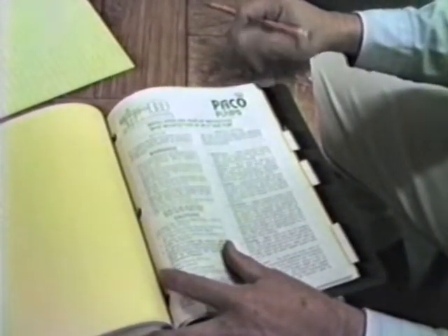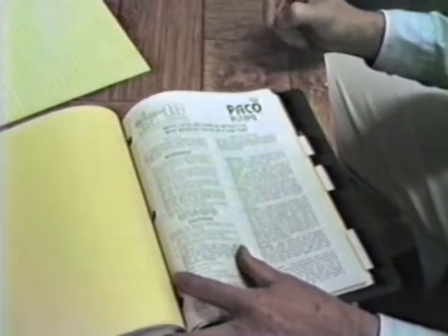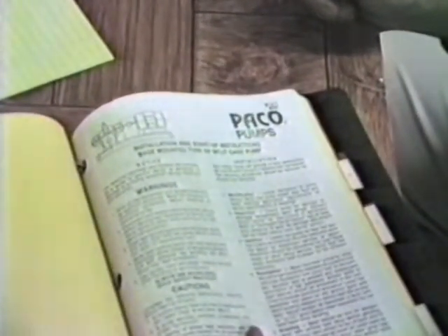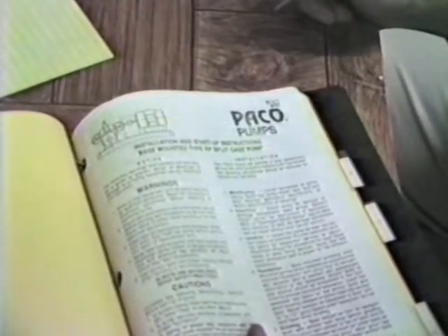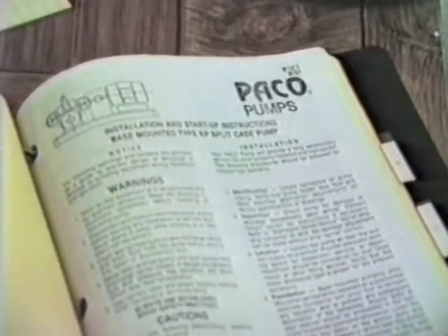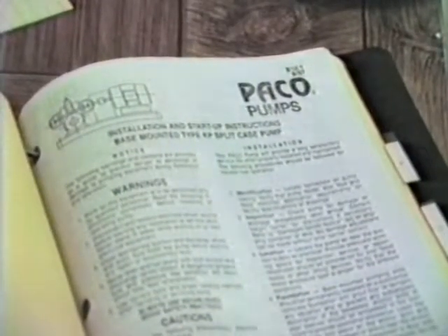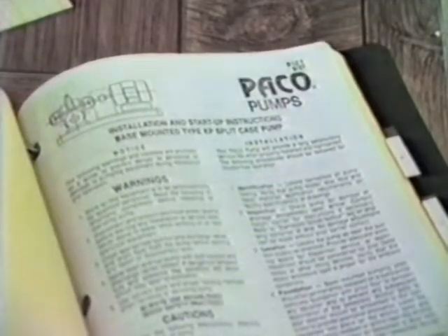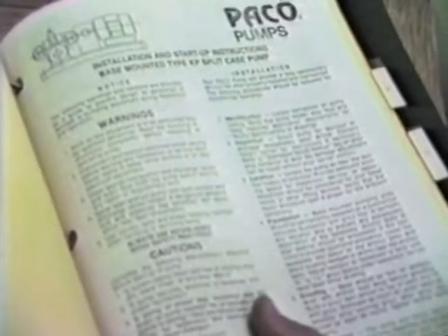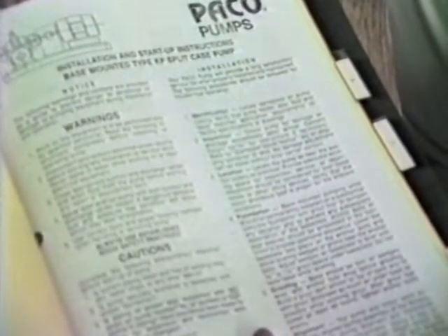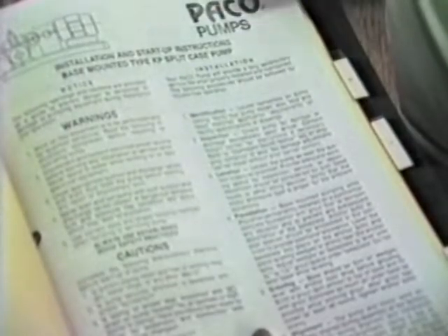In our system, we have installed two 20 horsepower Paco base mounted horizontal split case pumps. The operations manual gives real clear information, instructions for several key things to check and to maintain with the operation of the pumps. First of all, obviously it's important to keep the lubrication, checking and following through with the alignment. Electrical connections always need to be checked routinely. The manual gives a complete replacement parts guide, mechanical seal numbers.